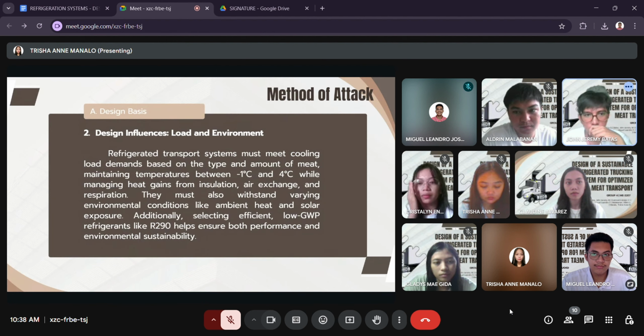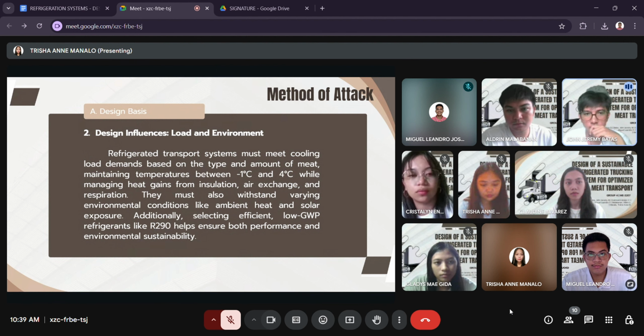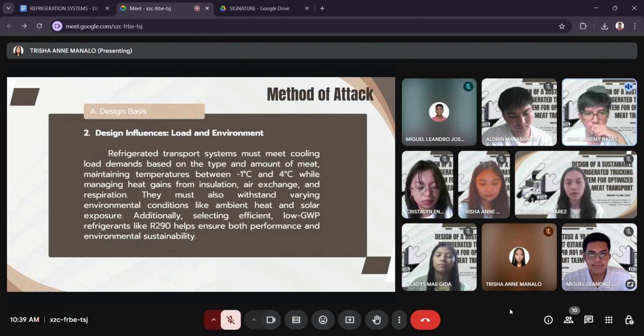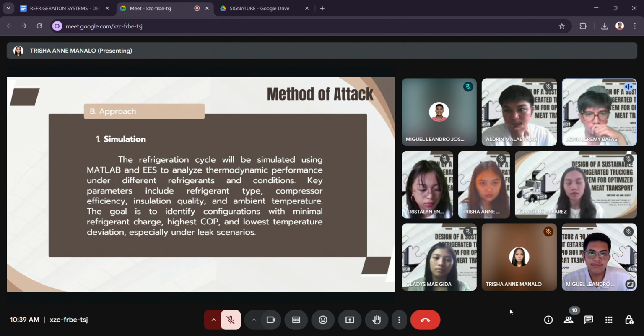Next, we considered key design influences. The refrigeration system must be capable of maintaining the proper temperature range between -1 degree Celsius and 4 degrees Celsius, regardless of the type and quantity of meat. At the same time, it must account for various sources of heat gain, including insulation limitations, air exchange during door openings, and environmental exposure like solar radiation. Choosing a refrigerant such as R290, which has a low global warming potential, also contributes to both system performance and environmental responsibility.